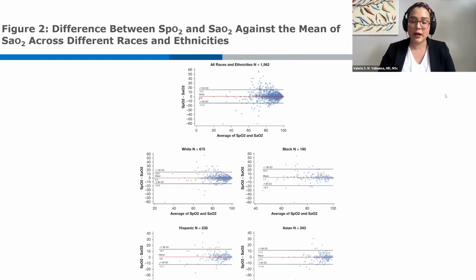And another limitation that we have discussed before, and an interesting one that maybe we can talk a little bit more about, is that we don't know which pulse oximeter was used to measure each one of these gases. This is worldwide data. We have data from Germany here, and we have no idea which pulse oximeter they're using there. However, I will put the limitation out there with the caveat that the great majority of modern pulse oximeters work with a very similar principle. There are not too many, if any, that I know of that work with a different design principle. And so it is our inclination to think that this is more of a class effect, based on the design, rather than Masimo's pulse oximeter being the one that works. Maybe that will become the thing once one of these companies decides to make a better pulse oximeter. But as of right now, the great majority of them work very similarly. So comparing one brand versus another was not something we were looking at. That was another limitation of our design.